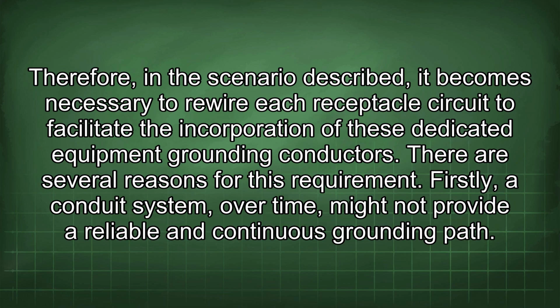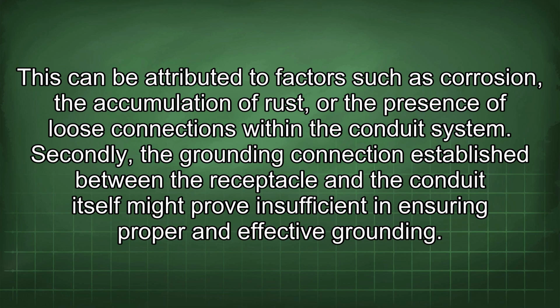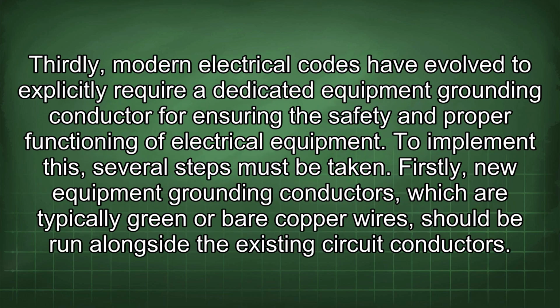Firstly, a conduit system, over time, might not provide a reliable and continuous grounding path. This can be attributed to factors such as corrosion, the accumulation of rust, or the presence of loose connections within the conduit system. Secondly, the grounding connection established between the receptacle and the conduit itself might prove insufficient in ensuring proper and effective grounding. Thirdly, modern electrical codes have evolved to explicitly require a dedicated equipment grounding conductor for ensuring the safety and proper functioning of electrical equipment.